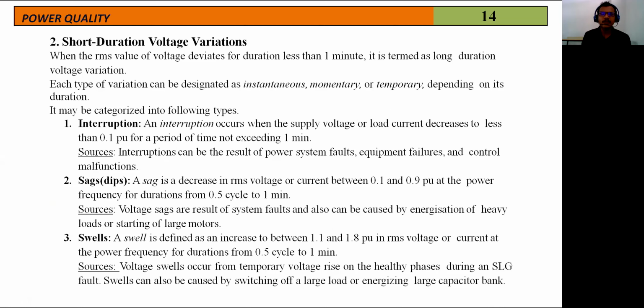Coming to the next one, short duration voltage variations. In a short duration voltage variation, within a small time, the magnitude of voltage changes. There is no rapid change like a transient. When the RMS value of voltage deviates for a duration of more than 1 minute, it is termed a long duration voltage variation. If the same time period is less than 1 minute, then the type of variation is known as a short duration voltage variation.